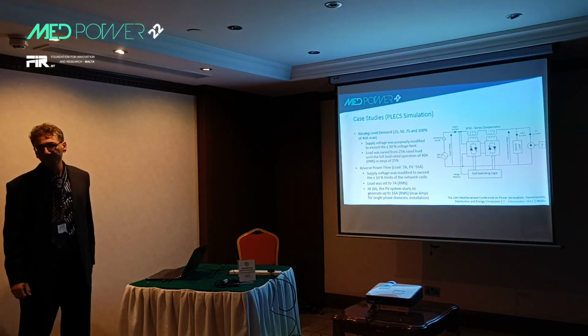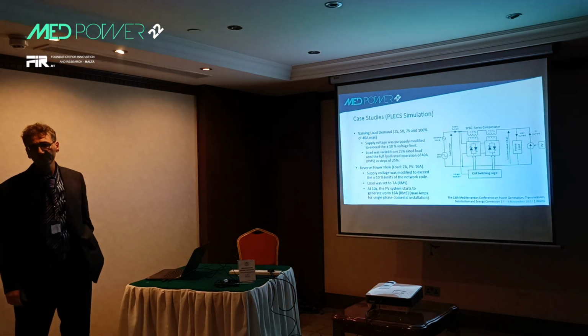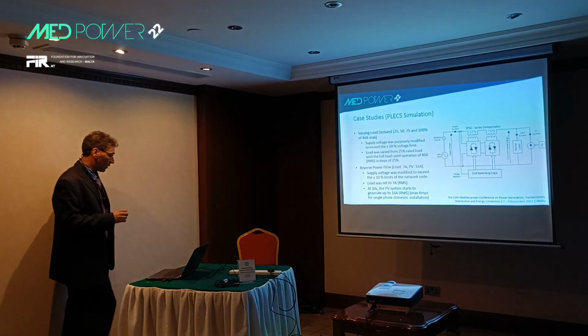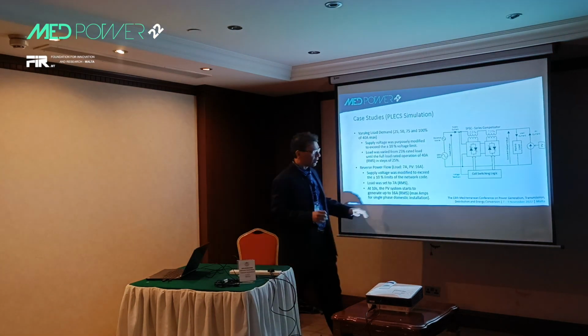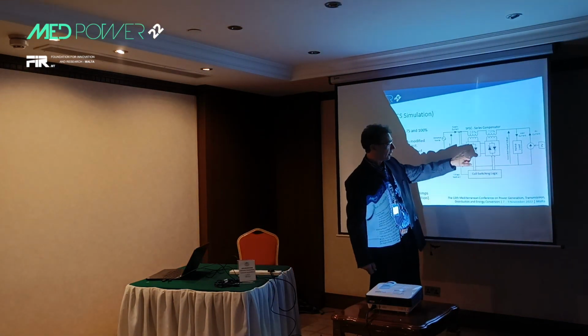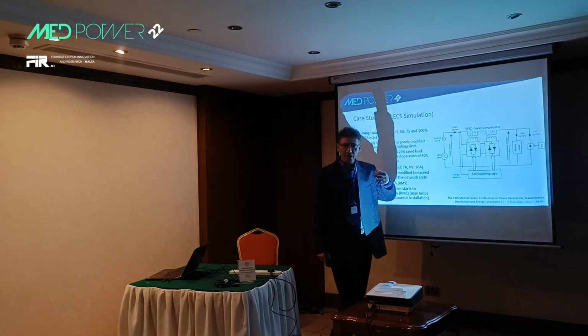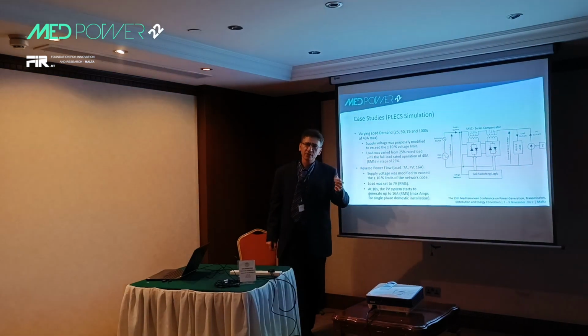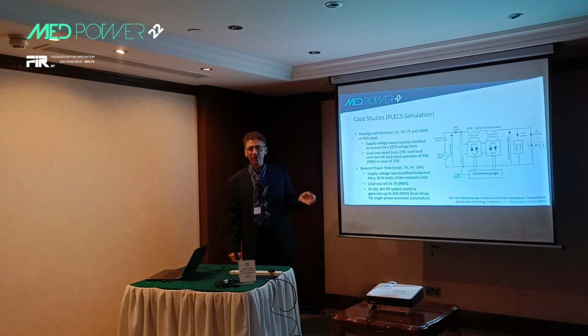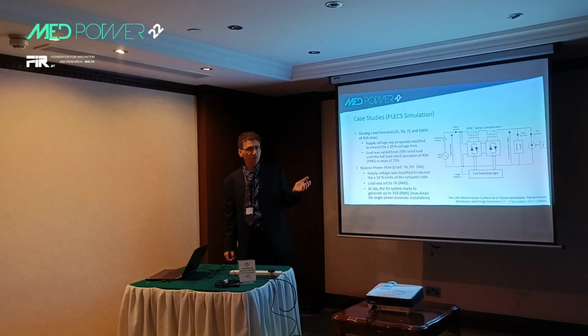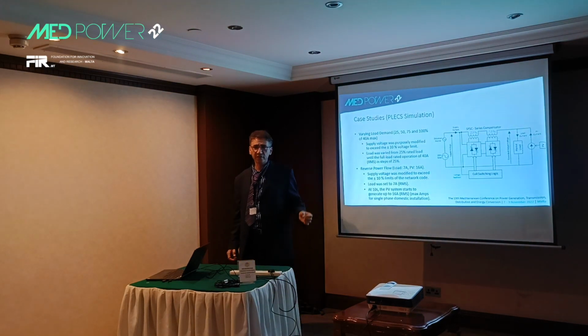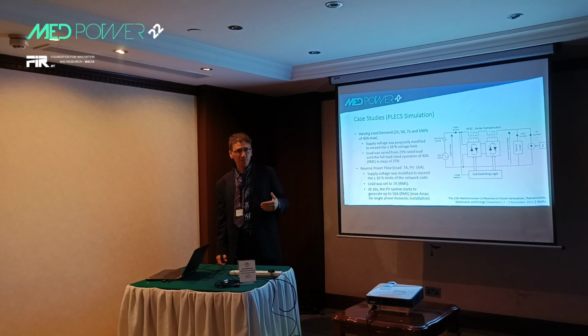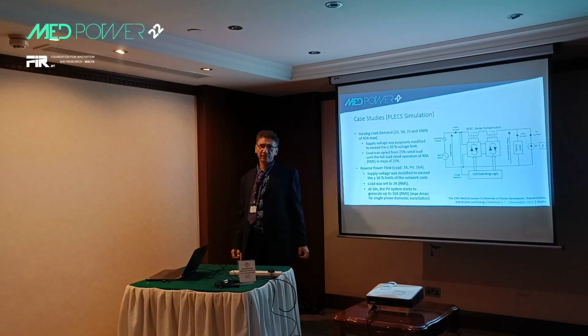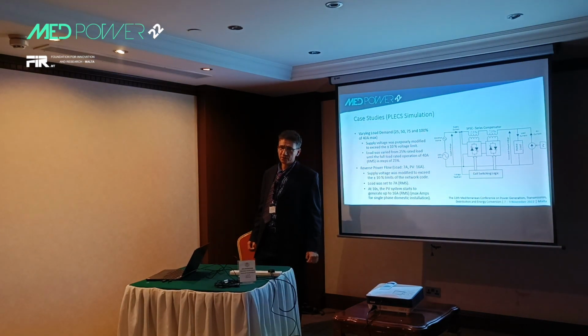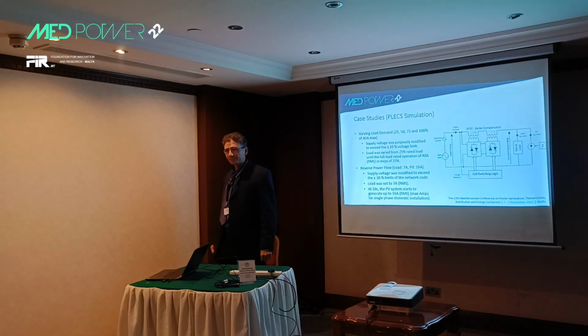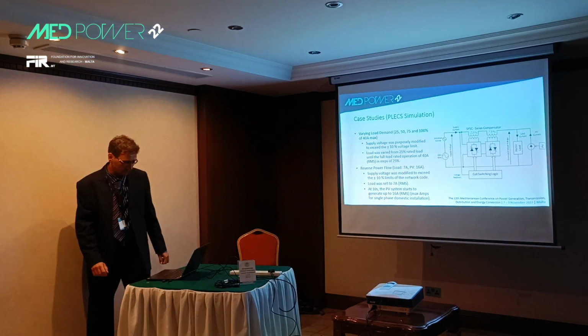Because I think that it will also introduce some losses, no? The losses are negligible because the only losses that you are going to have are over here, and this is the low voltage, low current side of the coil. So you have hardly any losses, and for thyristors, once they are on, the voltage drop is very small, about 0.3 to 0.5. So we are expecting this equipment to be about 99.5% efficient. Okay, thank you very much again.